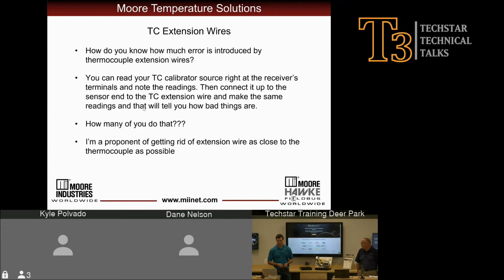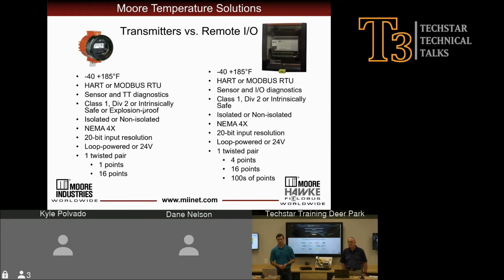But another way that we can reduce the amount of uncertainty that's induced into our temperature measurement is by eliminating thermocouple extension wire altogether. We can do this by wiring directly into transmitters or remote I/O devices. Most of these accept any RTD or any thermocouple, and they reduce the extension wire that puts error and uncertainty into our temperature measurement. So by wiring directly into a transmitter, we reduce the need for that additional wiring that's going to eventually over time corrode anyways. So we reduce the uncertainty as well as eliminate a future problem for us.